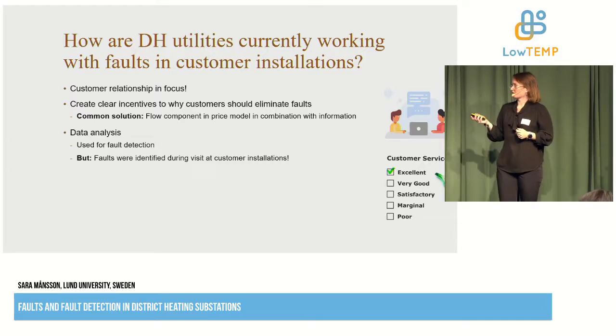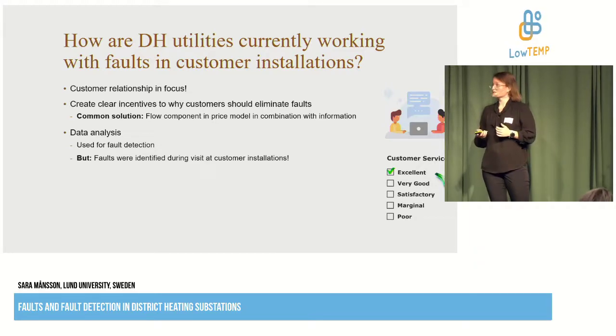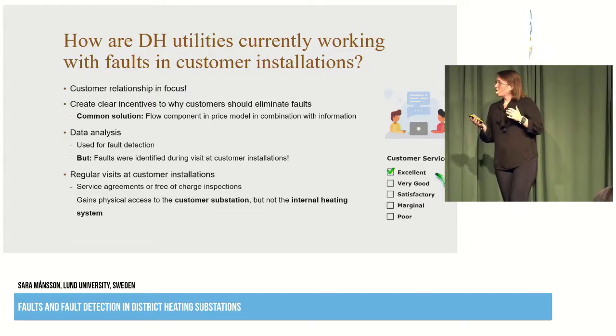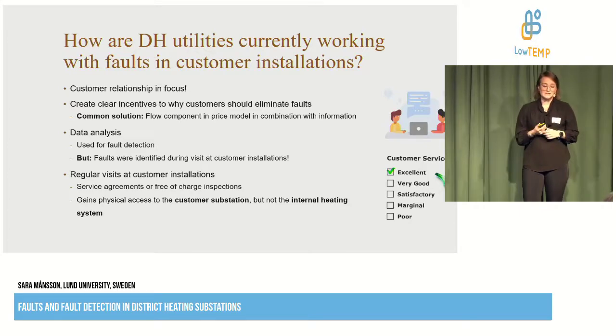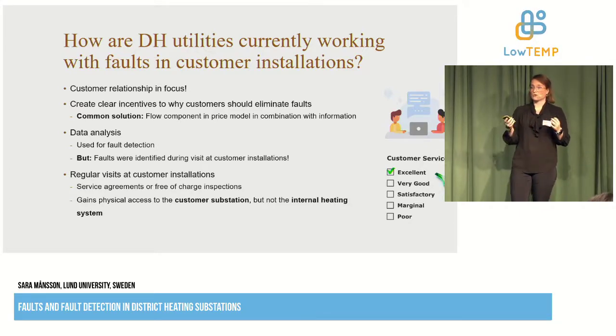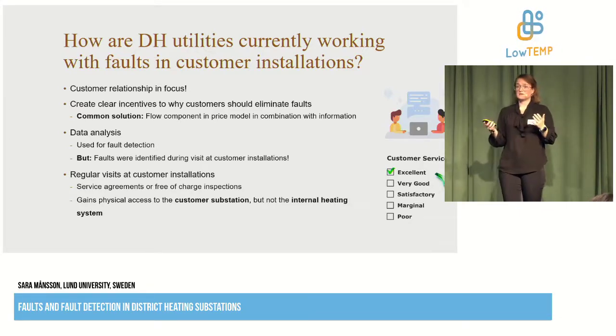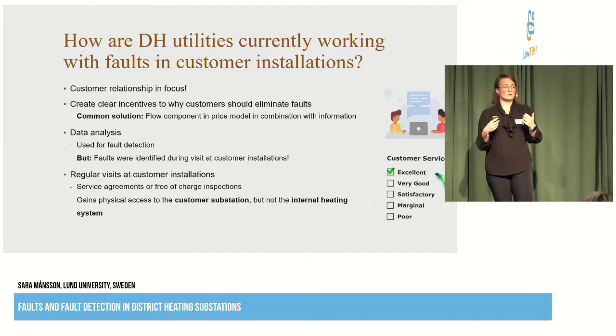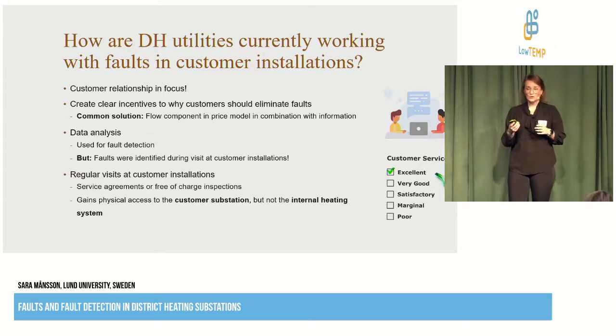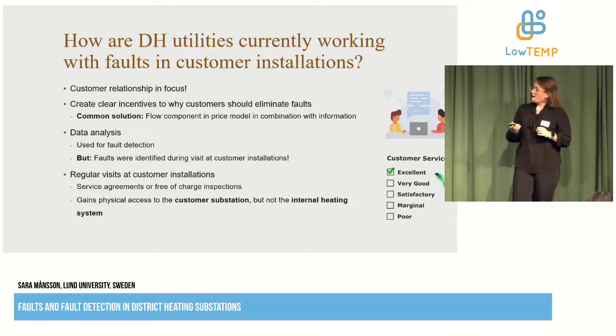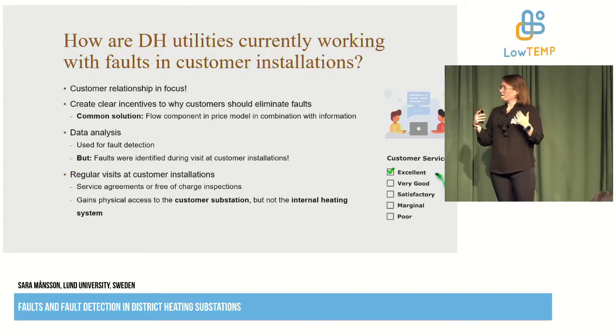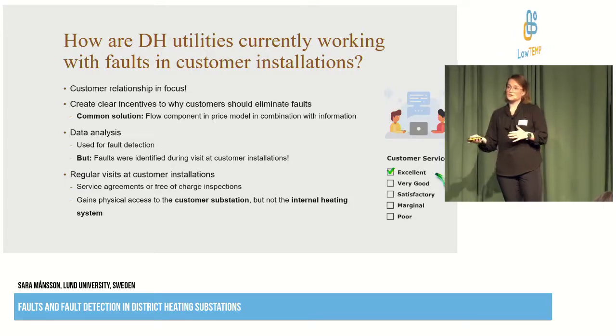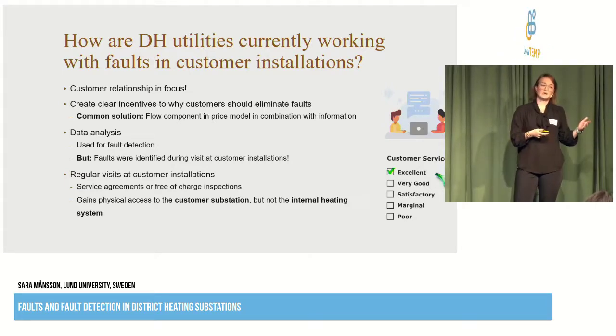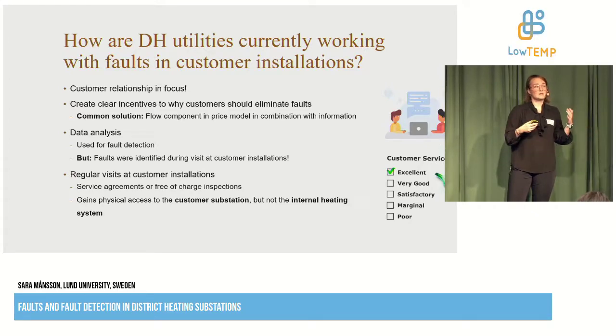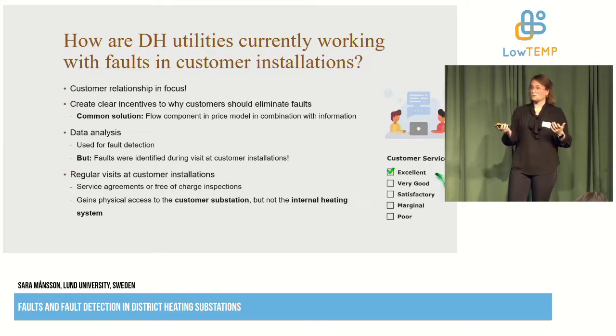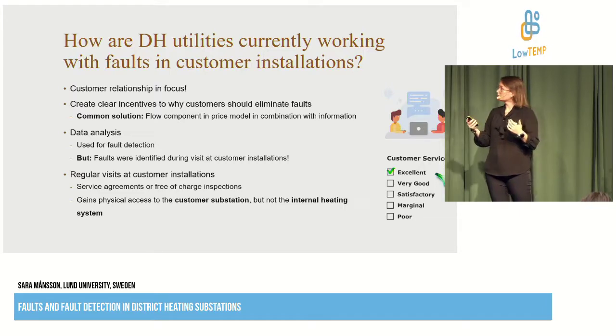Most of the faults were actually identified when visiting these installations, and many utilities performed regular visits at customer installations through service agreements, or sometimes even free-of-charge inspections, since this was such an important issue to them. They stated that this gave them physical access to the substation, but not the internal heating system. So if faults are located in the internal heating system, they might not be able to identify them, which is a problem because you want to find all faults.